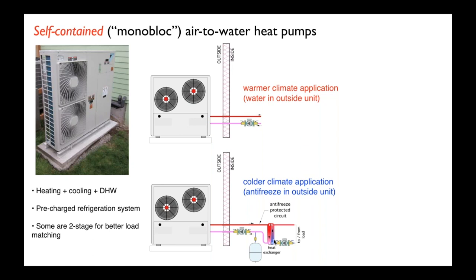Now, another option that is possible is down here, and that is to set up a generously sized heat exchanger. Typically, it's a flat plate stainless steel heat exchanger, and have the glycol between the heat exchanger and the outdoor monobloc heat pump, and then the balance of the system would operate on water. The key concept when you do this, a couple things here. You do have to have two circulators because we're creating two independent circuits there. And you want to make sure that you generously size that flat plate heat exchanger. We don't want to see what's called an approach temperature difference over about 5 degrees Fahrenheit. And that would be the difference between the hot antifreeze solution coming in from the heat pump and the warmed water leaving the heat exchanger and going to the balance of the system. We want that difference between those two temperatures to be as small as we can get it. So a practical limit is no more than about 5 degrees Fahrenheit.